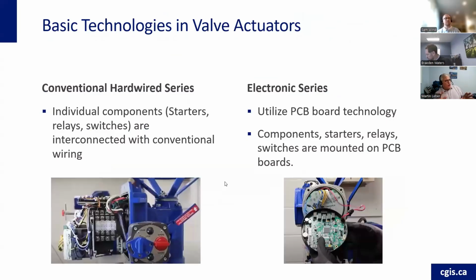Now we've come to the part where we want to discern between our actuators, the conventional hardwired series and the electronic series. We may interchange some of the acronyms here, but hardwired means the individual components, the starters and relays, are all interconnected with conventional wiring. The electronic series does have wires in it, but they're typically looms interconnecting the PCB boards, so the components, starters and relays are all mounted on PCB boards. I'm going to show you an example right now. This is your conventional contactor, and what this does is it starts the motor. It's really a relay, and whichever side of the contactor is started up allows it to turn clockwise or counterclockwise. So this is a typical contactor that you'll find in a conventional hardwired actuator.